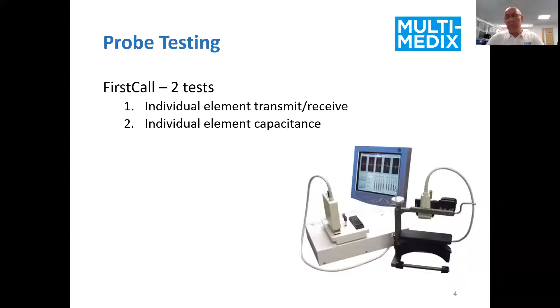We're also going to do an individual element capacitance test. Now, we don't actually need to be in the water tank for this, but it usually runs automatically whilst we've still got it in the tank. And that's going to tell us something about the electronic characteristics of our cabling and our array assembly. And that's really useful because that tells us a lot about the defects that we might see. I'm not sure how many people focus on the capacitance graphs in the reports, but it does start to tell us some really useful information.